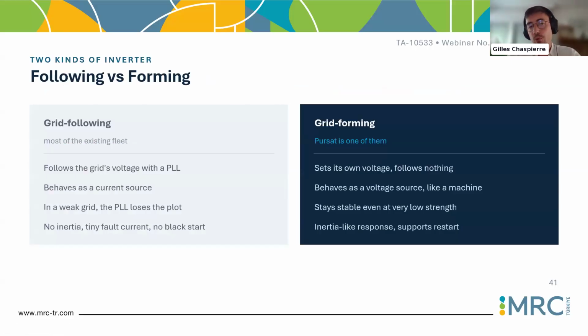So, a very, very, very important topic, but I guess everyone is aware. The majority of the power electronic converters in our system today are grid following. Grid following simply means I measure, through a phase lock loop, the voltage at the terminal, at the point of connection, and based on this voltage measurement, I inject a current. Since I rely on the external voltage reference, each grid following asset needs a sufficient amount of voltage stiffness to behave correctly. Otherwise, by simply measuring the voltage, you change your current injection, and the change of this current injection at the point of connection will itself impact the voltage you measure, and you enter a positive feedback loop, which can lead to growing oscillations.